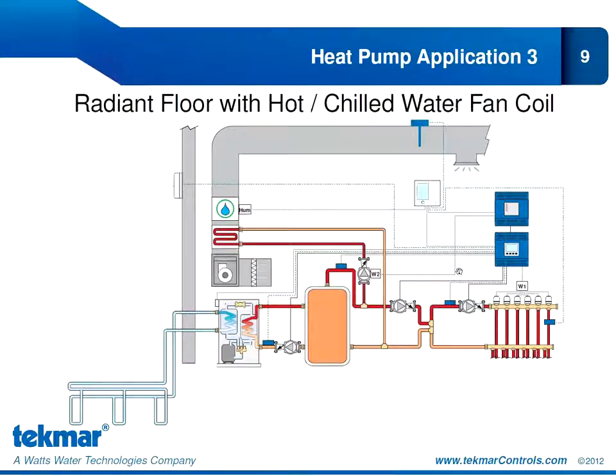Our last heat pump application shows the water-to-water heat pump. Now, since water is being used to distribute this energy to the building, we need to pair our 557 thermostat with the 406 house control. In heating mode, this buffer tank would be filled with hot water. Our first stage of heat would be the radiant floor. Our second stage of heat would be the fan coil, controlled with the W2 relay connection.